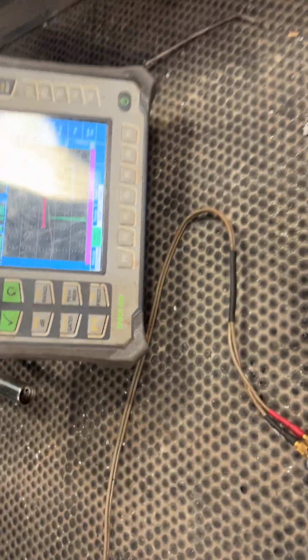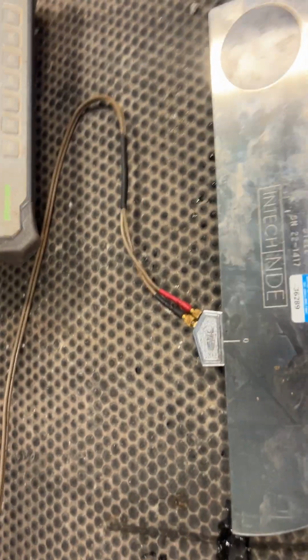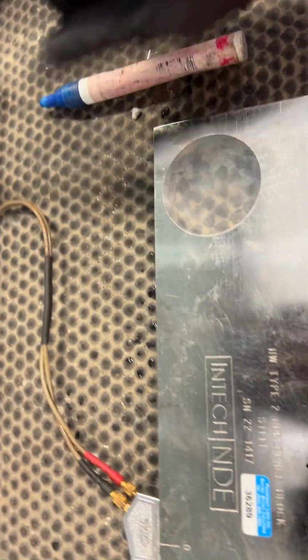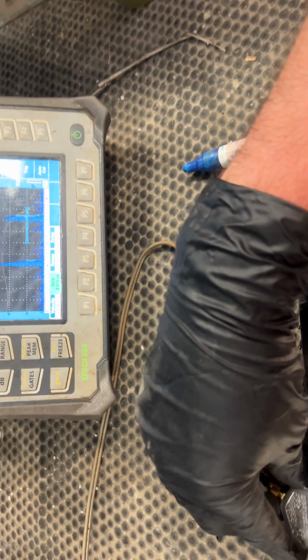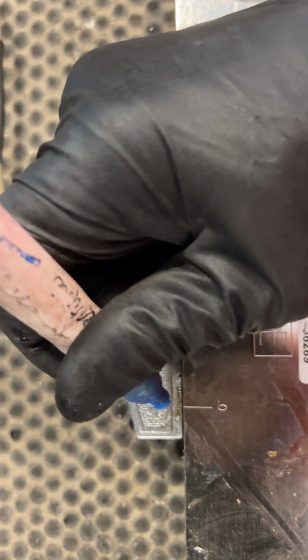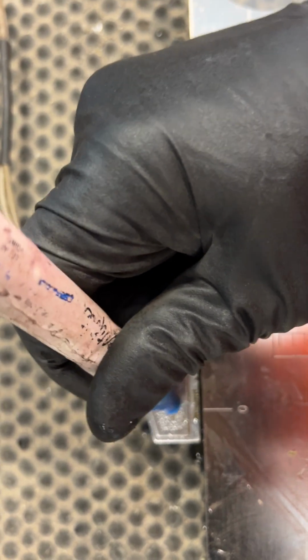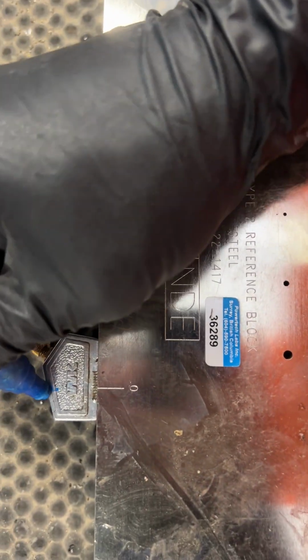Now we got a 4-inch calibration, which might be more than we need, but our 0 offset for our probe is right and our velocity is right. The other thing we should do now, oh, that doesn't matter, because we're not going to get it right anyways, is right now we've maximized our signal. Let's do that peak memory again. When you maximize your signal, you can tell where the signal's coming out of your probe. So you make a mark at 0. That's where you need it, because that's your index point. That is where, from the top of your probe, your signal's coming from.